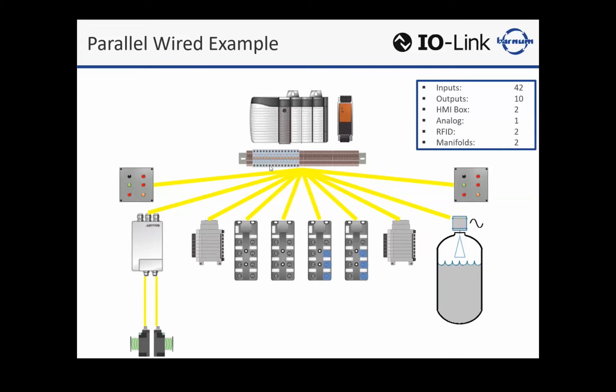The larger blocks are just representing output protection, because in any of our outputs, indicators, valves, things of that nature, we need to go to a circuit breaker or fuse to protect that output device. And again, we're adding sequential input, output and analog cards in the PLC rack to make sure we have enough dedicated inputs and outputs on our PLC itself. And you can see, as you add more inputs, we're going to need more input cards, as with more outputs. In terms of flexibility, if we need to add anything to the system and we maximize it here, we need to make sure we accommodate the panel space for additional terminal blocks, outputs, swing arms. We need to make sure our PLC can handle more input or output cards, because if something needs to be added in the field or later on in the design, right now our flexibility is very limited to what hardware is out there.